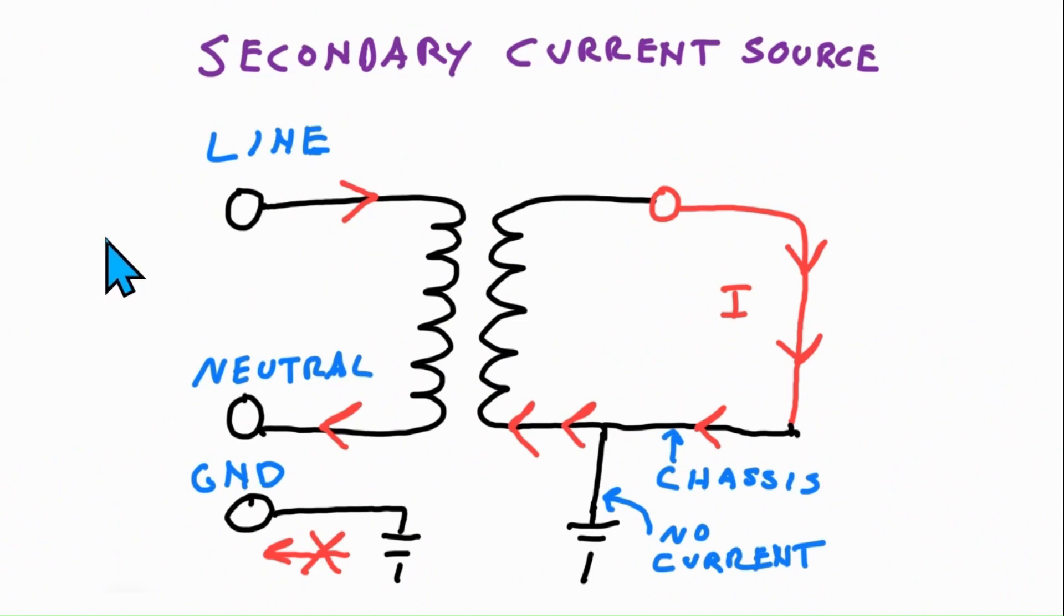The reason appliances are able to use a grounded chassis as an intentional path for current flow is because the source of current is from a secondary circuit like this. This is an isolation transformer that represents a secondary circuit. It could be a spark module, a DSI module, or just be a transformer.